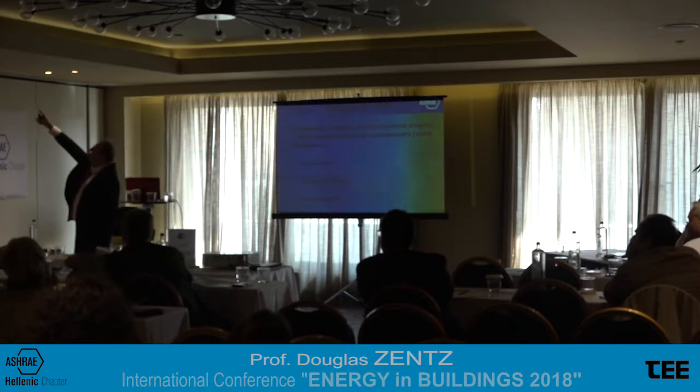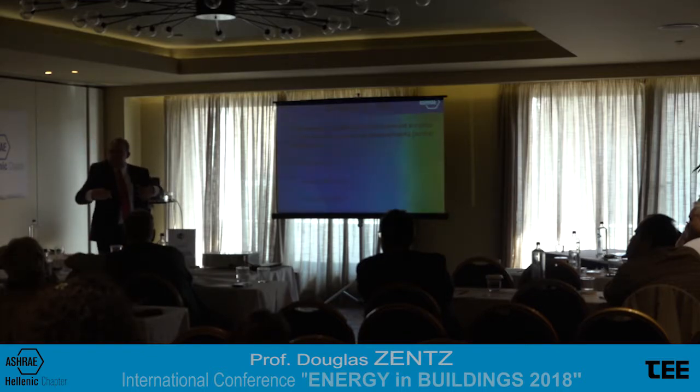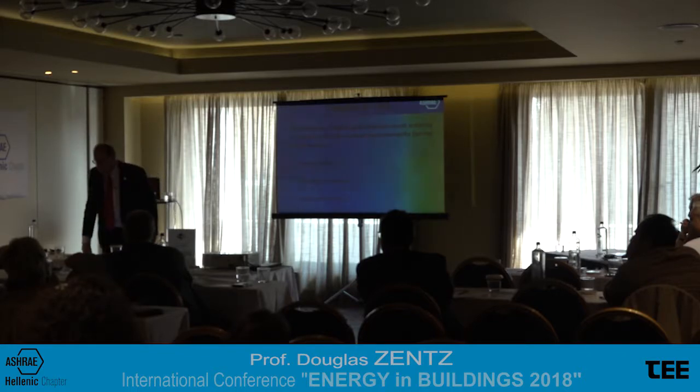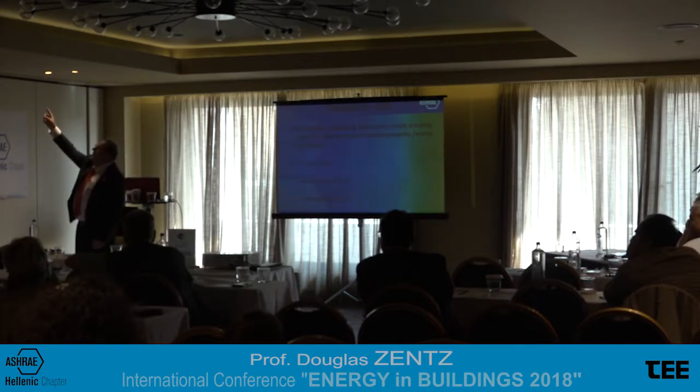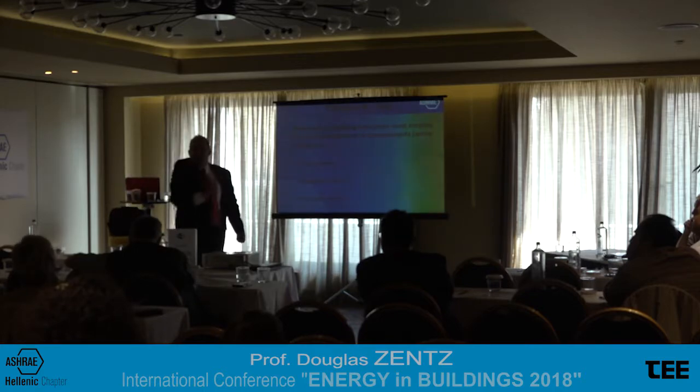So the air coming out of the diffuser is whipping along the ceiling right there, much faster than the air around us. It creates a low pressure zone. Down here where the dirt is, it's higher pressure. The dirt migrates its way up and collects at that low pressure zone. And then if it's like a lot of buildings, you have corrugated ceiling tiles that are nice materials to grab dirt as it whips by.